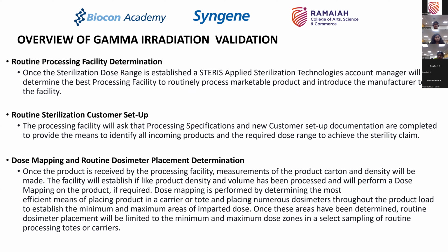Once the product is received by the processing facilities, measurement of the product carton and density will be made. The facility will establish if the like product density and volume has been processed and will perform a dose mapping of the product if required. Dose mapping is performed by determining the most efficient means of placing a product in a carrier or a tote and placing numerous dosimeters throughout the product load to establish the minimum and maximum areas of imparted dose. Once these areas have been determined, routine dosimeter placement will be limited to the minimum and maximum dose zones in a select sampling of a routine processing tote or carrier.